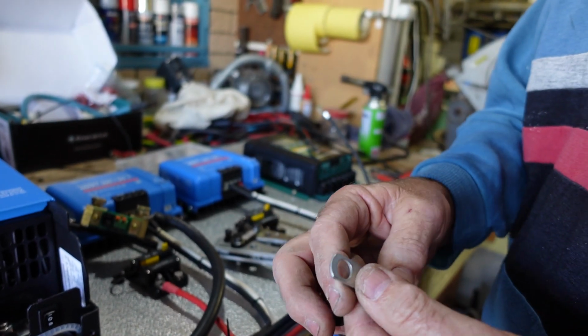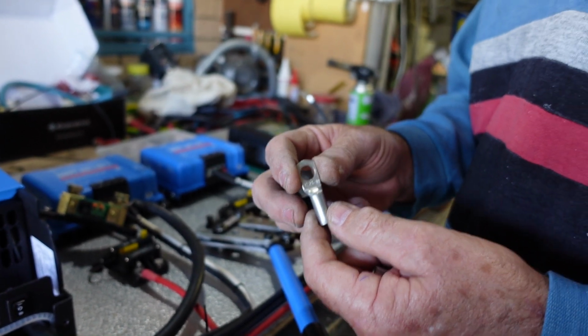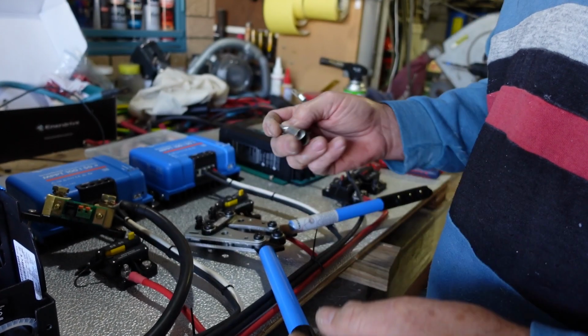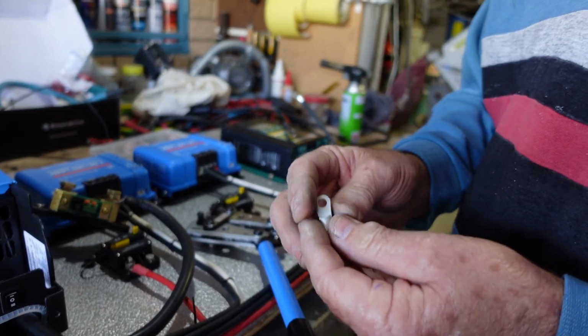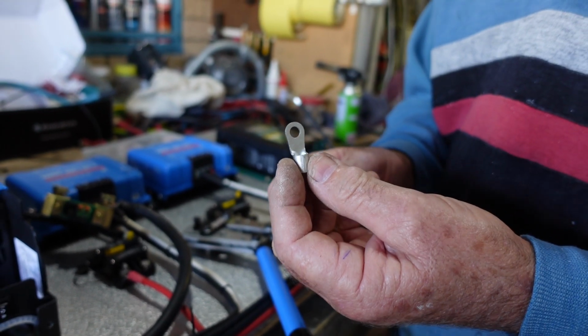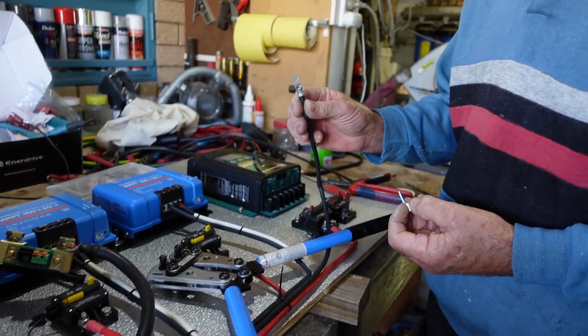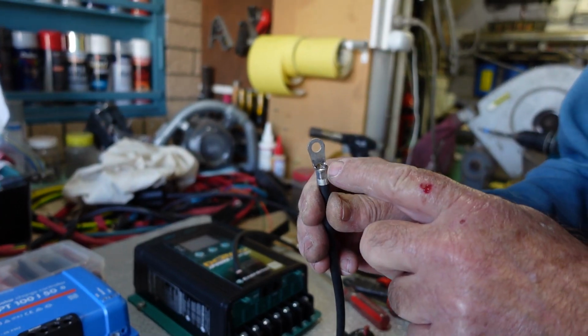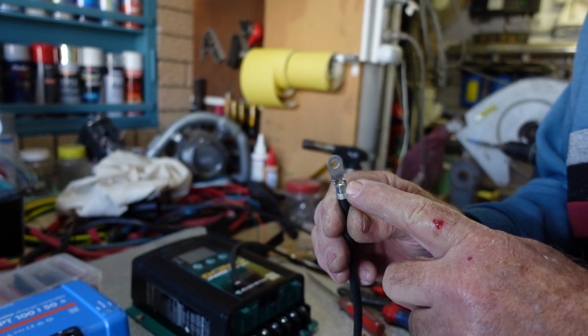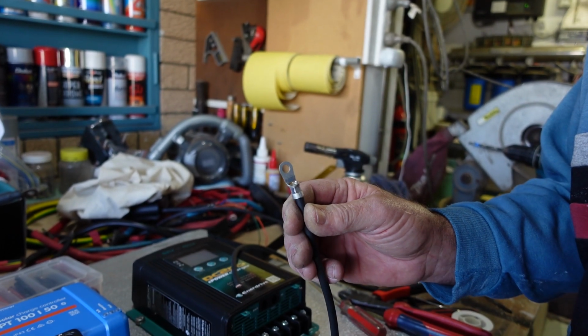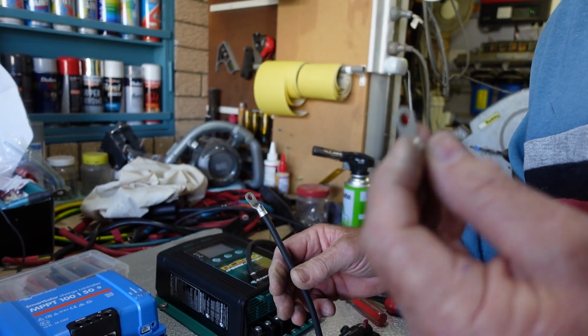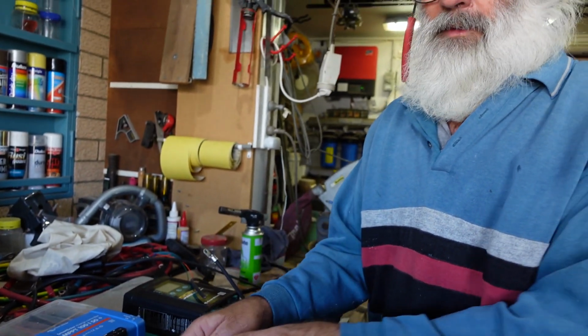When it comes to crimping, if you don't have the right tool, or you're going to use one of these cheap Chinese tools, I highly recommend you try and get the open terminal. Because what you can do is crimp it first, and as you were seeing just a few minutes ago, then you can fill the top of the unit with solder. So you've got both a mechanical and an electrical bond, and that is a good connection. If you just crimp it, you're asking for trouble, especially with these cheaper tools. So solder everything, and then you know you're right, because that's how fires start. If you get a bad connection it causes heat, and heat causes fire.